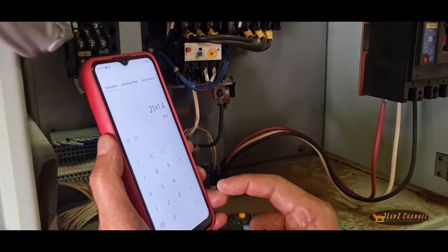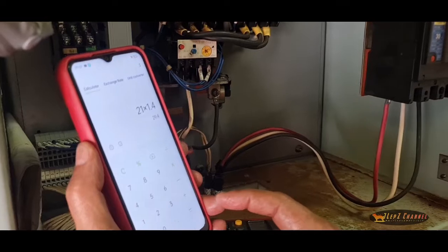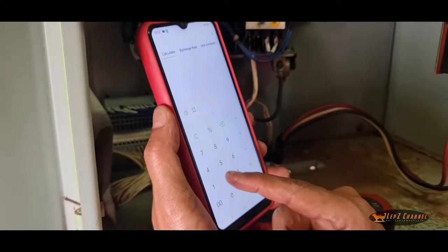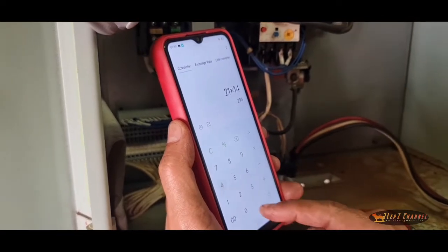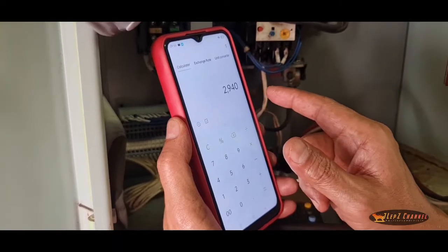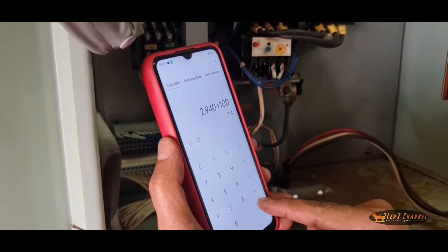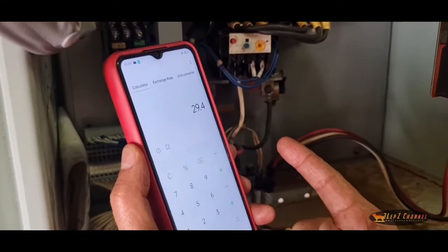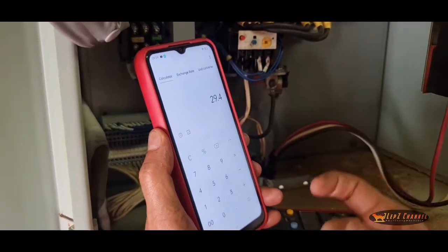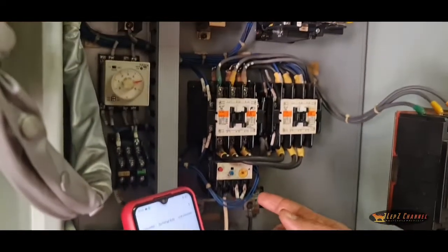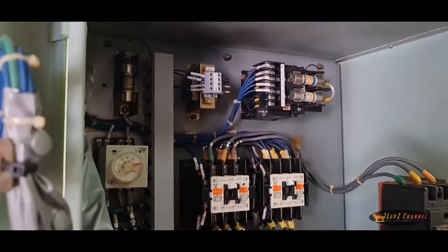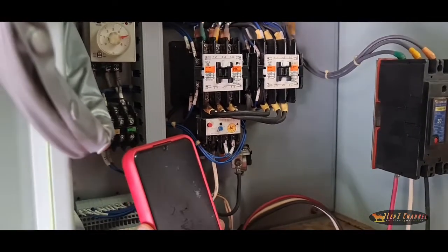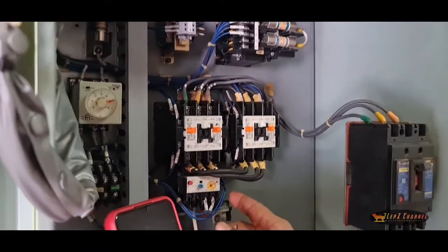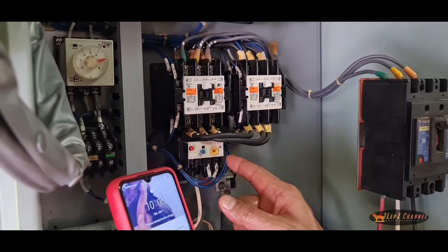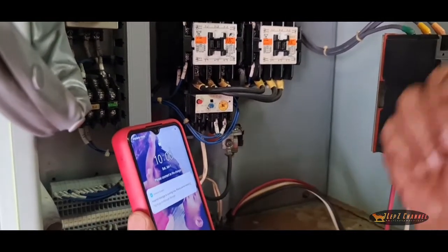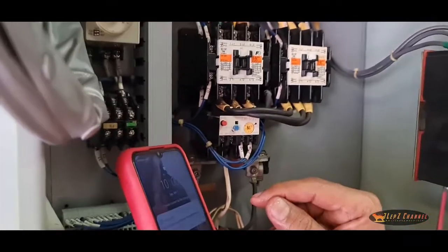Now we get the maximum current of 29.4. You see, 21 times 140% equals 2,940 divided by 100. The maximum allowable setting of an overload relay for this engine room fan is 29.4. But since this motor is not the original, it is an old one, the replacement of the burnt-out motor, you can see that the maximum for the overload relay model TR-2L is 26.